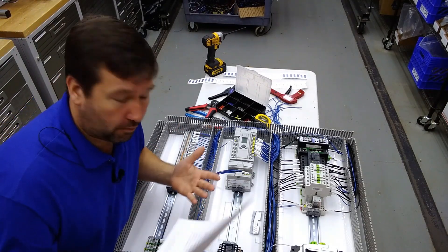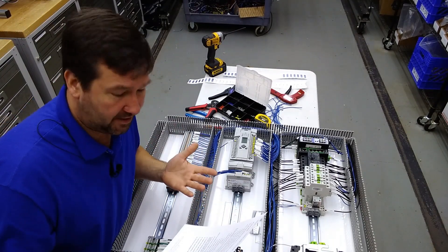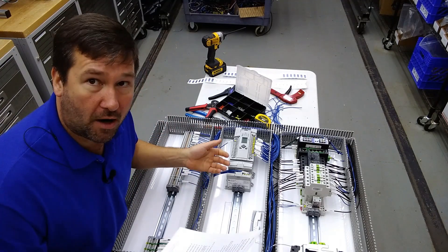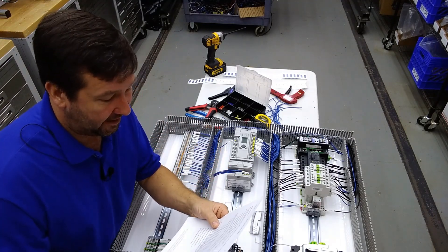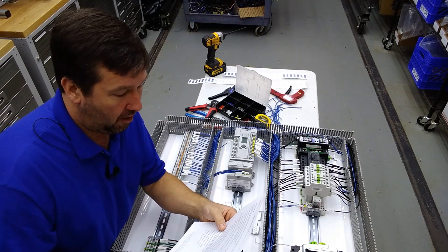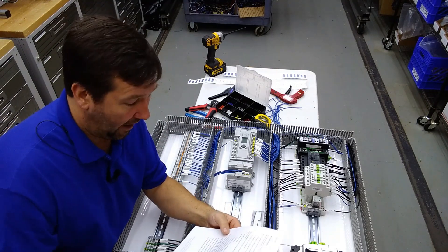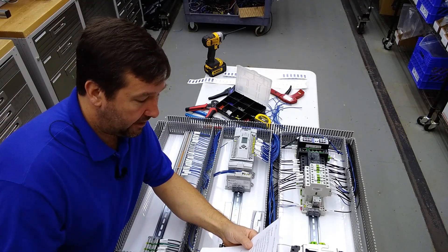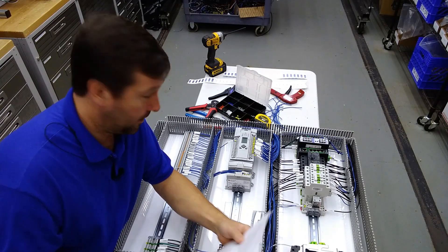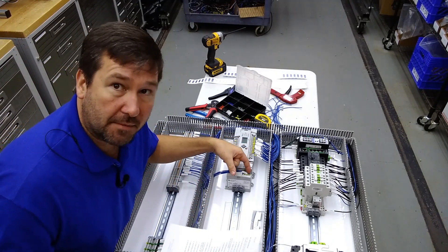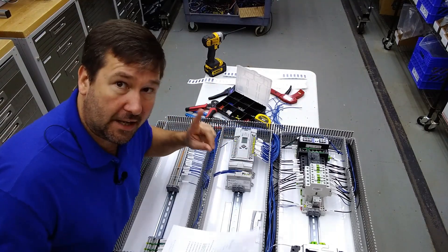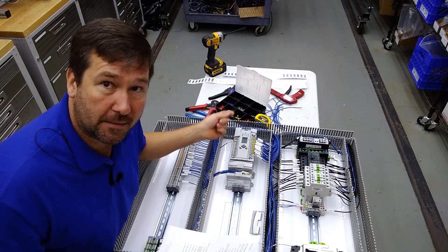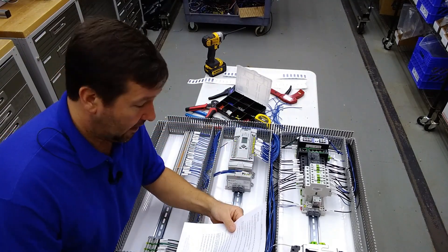29.3.4 addresses ways that you can connect wires to terminals. It says a connection method to a terminal for a component shall be made by: A - wire inserted directly into a pressure wire terminal of a component. And that would be your typical screw terminal. So you can just stick the bare wire into the terminal.